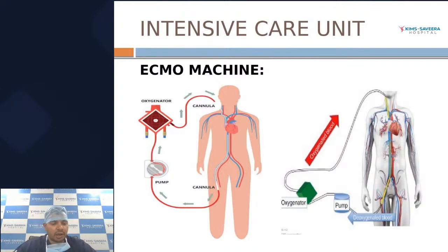So what is the main function that is required of the lungs and the heart? The basic function of the lungs is it takes in fresh oxygen, sends it to all the parts of the body, and it takes out the carbon dioxide and sends it out of the body. So when it is not able to do that exchange, what this ECMO machine does is it uses an external oxygenator. So whatever blood is drawn through the cannula is passed through the pump as well as the heat exchanger, and then it is taken to the oxygenator. The oxygenator basically provides a rich oxygen supply to the blood, as well as it takes out the carbon dioxide through the sweep gas mechanism that is present in the machine. So once the blood is enriched with oxygen, it is again sent back to the patient.